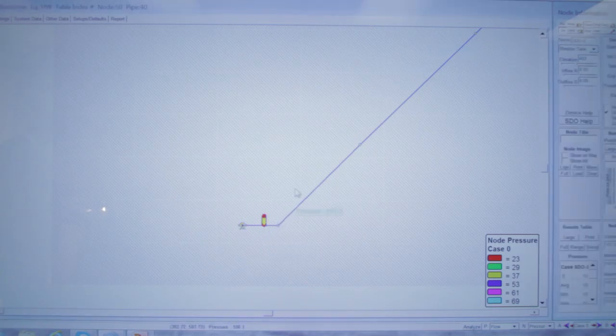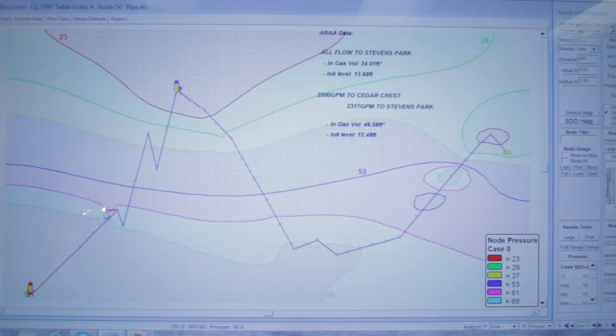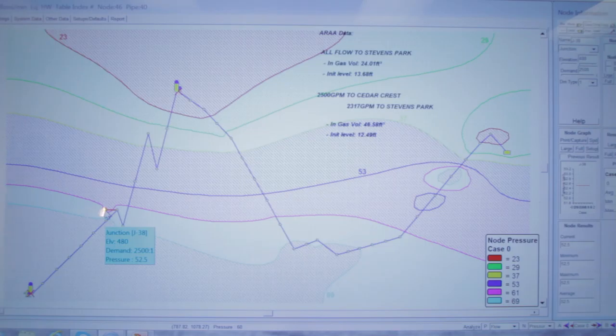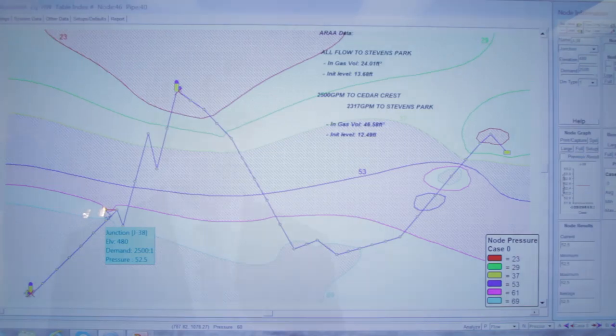We also have a surge vessel here, and for the point of this demonstration I'm going to go ahead and turn that off. This is our first customer — a golf course where we're filling into a pond. At that particular node, our pressure is 52.5 psi. We have a sustaining back pressure valve so that we sustain a back pressure in the system as this valve opens up, so we don't draw the water out of the system. There's a huge elevation change — we could easily drain out this whole pipeline as we're filling the pond. So we need to sustain the back pressure in the system.